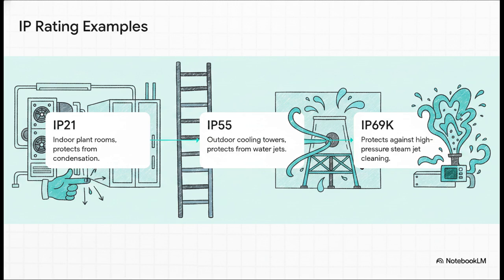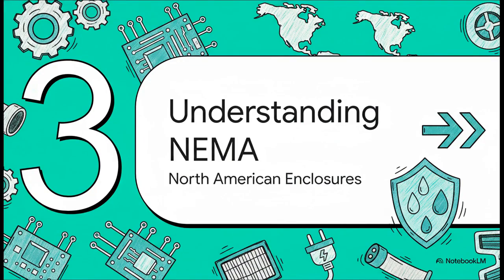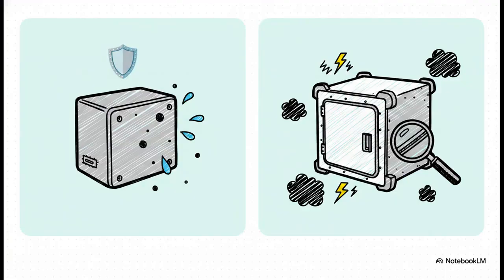Real heavy-duty stuff. Now, while IP is an international standard, North America actually plays by its own set of rules. So let's jump to Section 3, understanding NEMA enclosure ratings. Okay, so this is where it gets really interesting. The NEMA rating system looks a lot like the IEC's IP codes, but they are absolutely not exact clones. Remember, IP codes only care about blocking solids and liquids. That's it. But NEMA? NEMA goes way further.